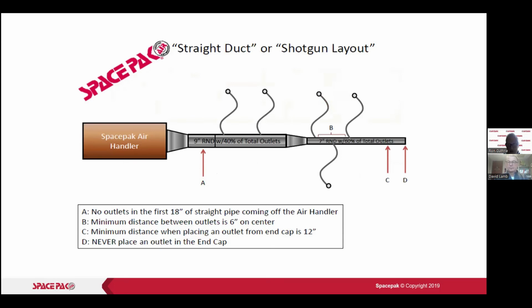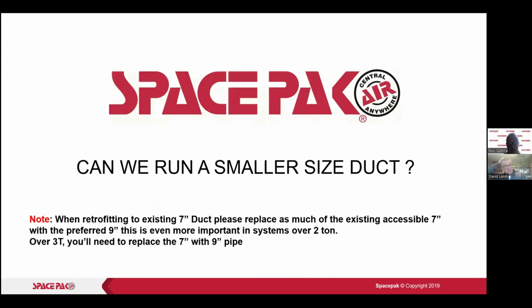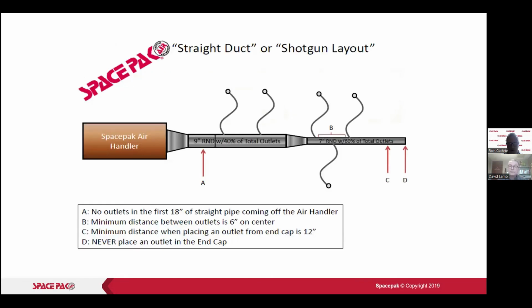In that, you'll find these pictures, and a lot of times guys overlook that these pictures are in relation to the 2430 air handler. It's recommended for the 3642 or the 4860 to actually change all of the duct to 9-inch. But here on the 2430, basically what we're doing is on a shotgun, we're changing out the first 40% of the outlets to 9-inch. And then we're figuring, well, we've got less volume at the end here, so we're okay with 7-inch. So again, where to find this information is in the installation manual.